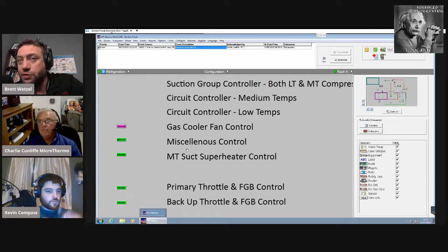You could also have one board or one section of communication that could actually be taking out the whole network. So sometimes what you have to do at that point, as we've discussed, is basically start breaking down the network. So if you've got 4 connections going out into the store, and the whole store keeps going intermittently on and off as far as communication, what you can do is unplug all the communication cables and plug in number 1.